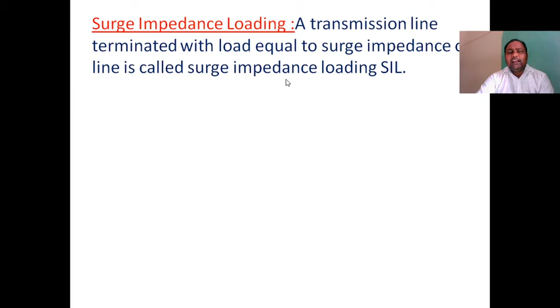So the formula for surge impedance loading is very important: power transmitted is equal to VRL square by Z0. Here VRL square is the receiving end voltage, where L stands for line to line, so it's the receiving end voltage line to line, by Z0. Normally the VR value must be substituted in KV. Z0 varies between 400 ohms to 600 ohms depending on the transmission line.